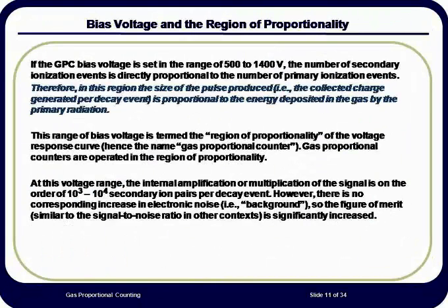One distinct advantage of counting in the proportional region of voltage is that the signal amplification factor distinguishes between alpha and beta particles, but the background count rate from lower voltages is not increased significantly. Thus, the signal-to-noise ratio, also referred to as the figure of merit, is increased. This makes detection of these particles more achievable at lower concentrations.